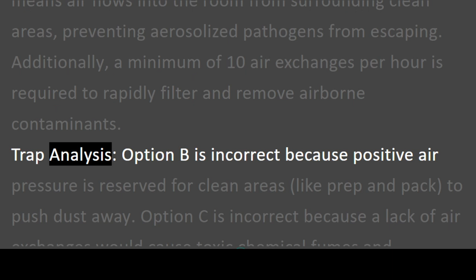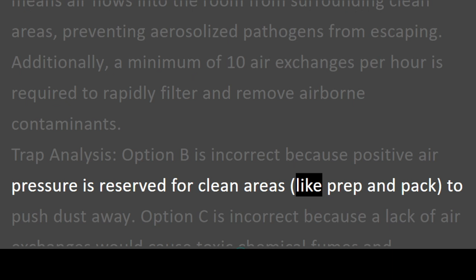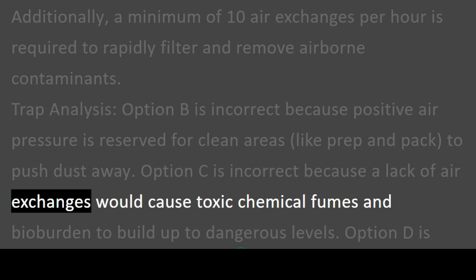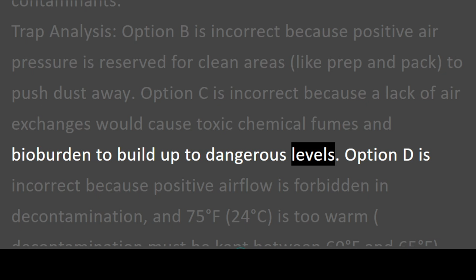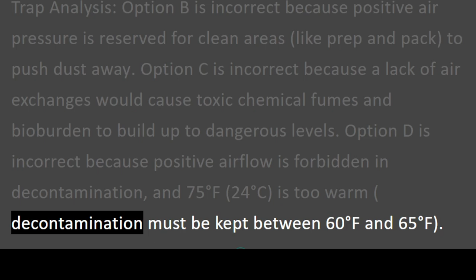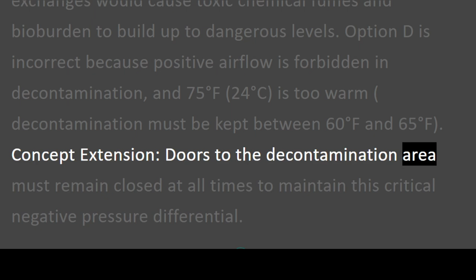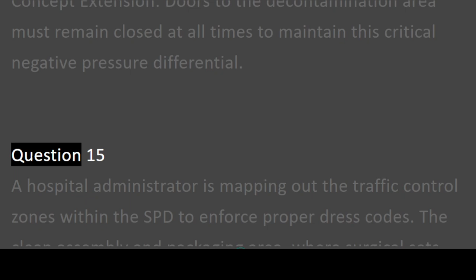Trap analysis. Option B is incorrect because positive air pressure is reserved for clean areas, like prep and pack, to push dust away. Option C is incorrect because a lack of air exchanges would cause toxic chemical fumes and bioburden to build up to dangerous levels. Option D is incorrect because positive airflow is forbidden in decontamination, and 75 degrees Fahrenheit, 24 degrees Celsius is too warm. Decontamination must be kept between 60 degrees Fahrenheit and 65 degrees Fahrenheit. Concept extension. Doors to the decontamination area must remain closed at all times to maintain this critical negative pressure differential.